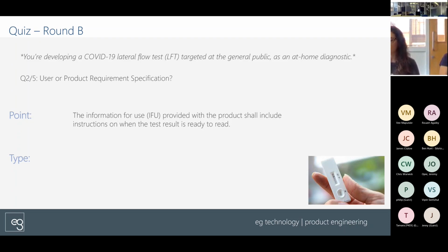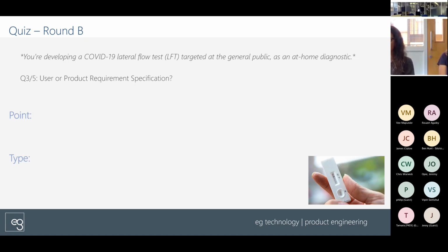What do people think? User or product requirement for this one? Yes, we've got a mixture this time, and that one was a bit harder. I said this is a product requirement, although it's slightly less clear. It could be a direct traceability from the previous one. The user just cares that it's easy to read. They don't mind whether that's because of a clear instruction in the IFU or the device speaks to them and tells them it's ready, or whatever method for letting them know that it's ready. Whereas the product requirement is a bit more about how you might do it to an extent, and a way to test that you've designed the product correctly.